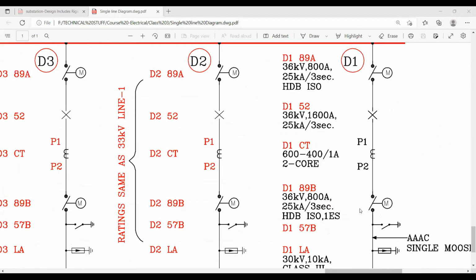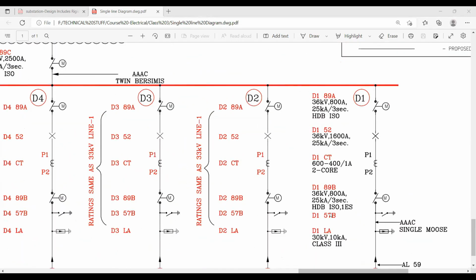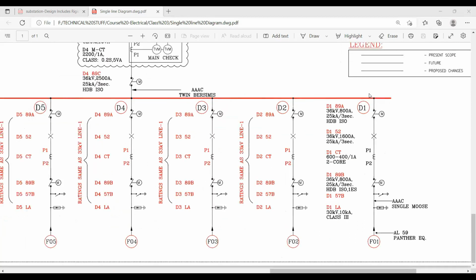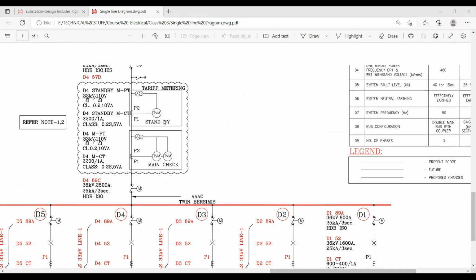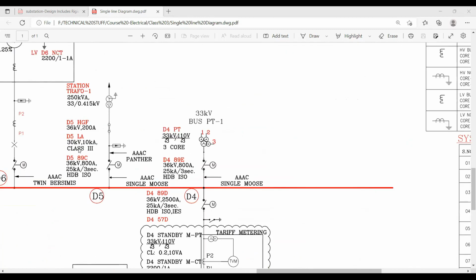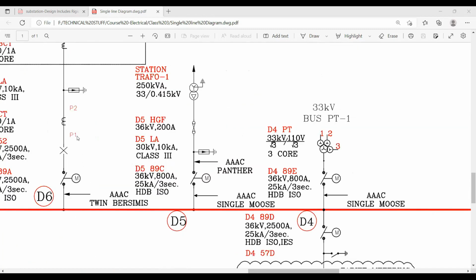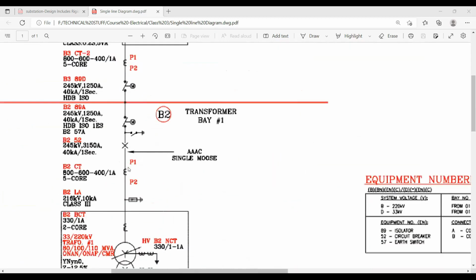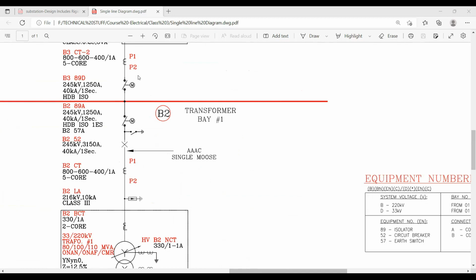And this is the representation like D1 LA, D1 89B, 57B, D1 CT, D1 52, D1 89A. And always in the CTs, we have the polarities P1, P2, team. Generally, we represent P1 towards the bus. This is the practice generally followed by every developer or utility. P1 should always face this side. You can see here, same CT, this is the bus, right? That's why P1 is facing this way. Here, in this CT, P1 is facing this way.